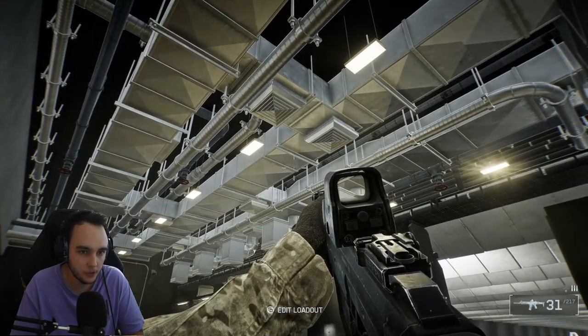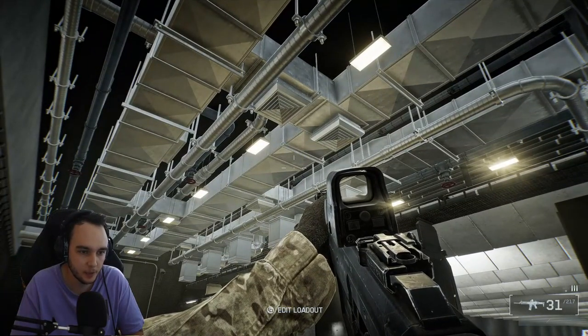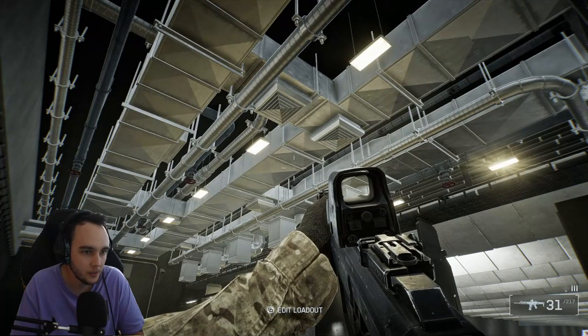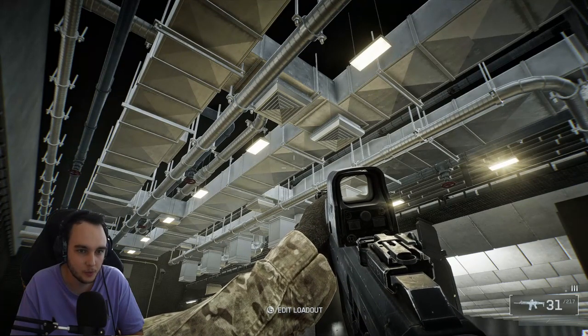I'm gonna give it a shot at maybe quickly redesigning it in a CAD program and see what happens, how it turns out. There's something I didn't really talk about, which is pressure. There's usually positive pressure or negative pressure in a room. And typically something like this shooting range, where, like I said, you'll have some smoke or gases, you'd see the room under a negative pressure.